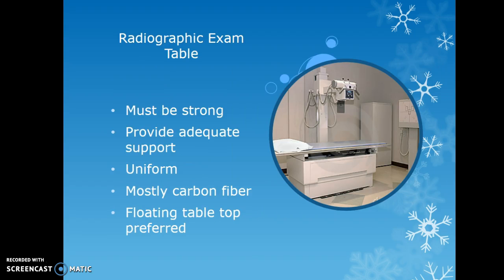The table must be strong, provide adequate support, and must be uniform — meaning the same composition from one end to the other, mostly carbon fiber. A floating tabletop is preferred. You don't see fixed table units anymore due to the movement required of patients and technologists. You may still see them in rural settings or very old facilities.